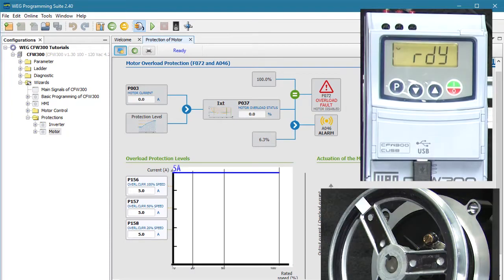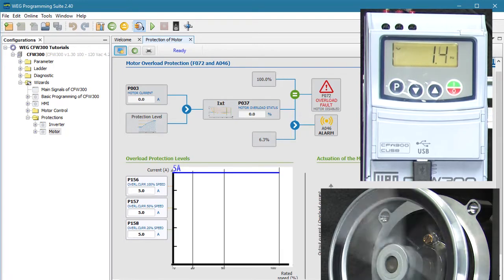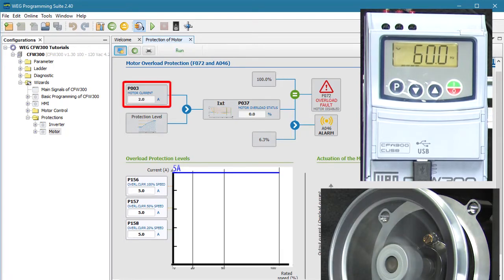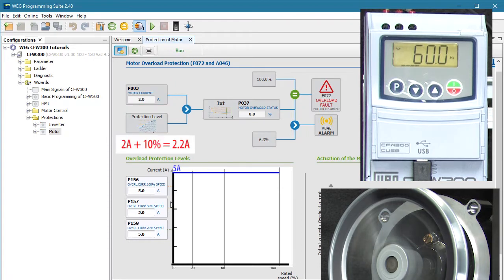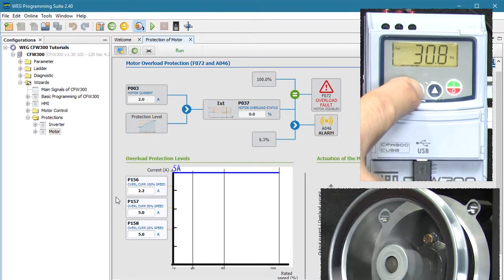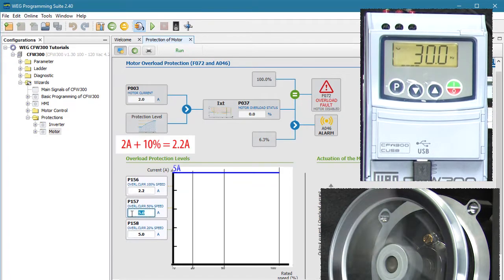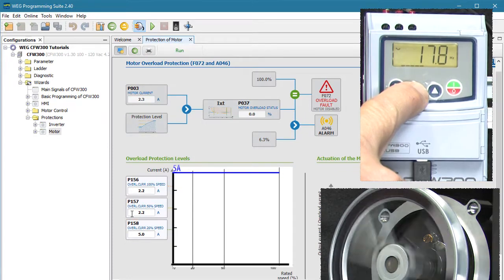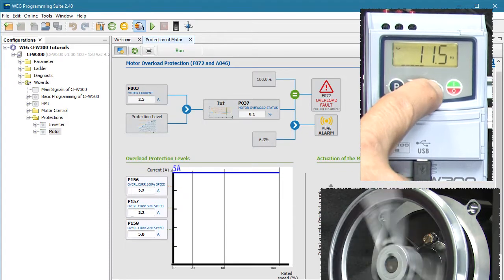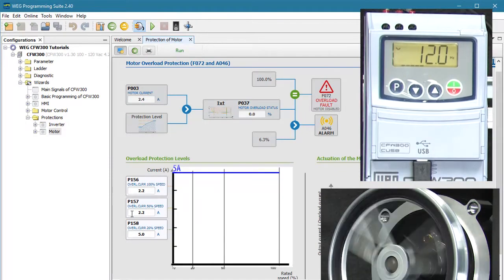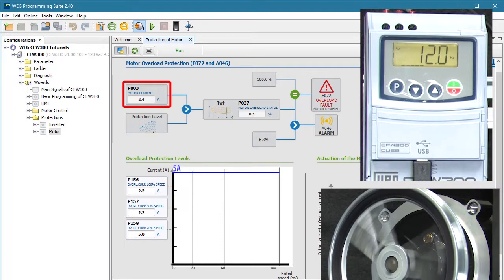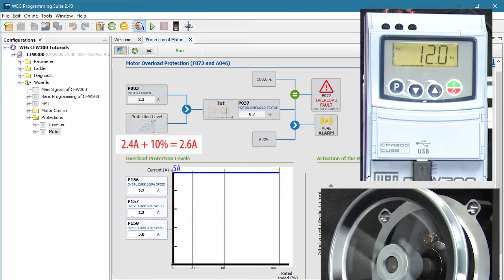Let's try this process on my motor. I'll crank it up to full speed at 60 Hz and we see the current is 2 amps, so I want to enter 2 amps plus about 10% here. I'll move the motor down to half speed and it's still drawing 2 amps, so I'll put the same number there. Finally, let's take the motor down to 20% speed, which is 12 Hz, and we see the current is 2.4 amps.